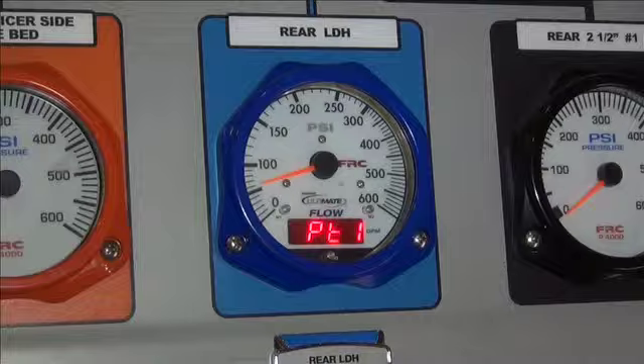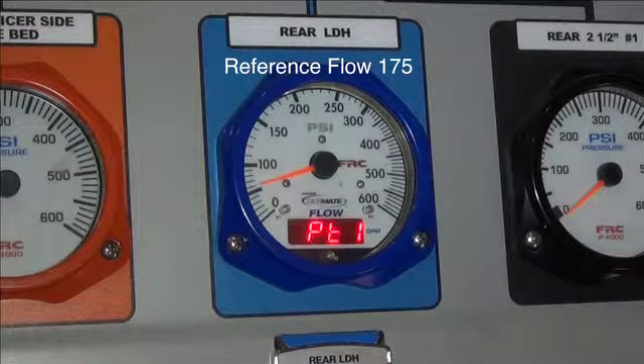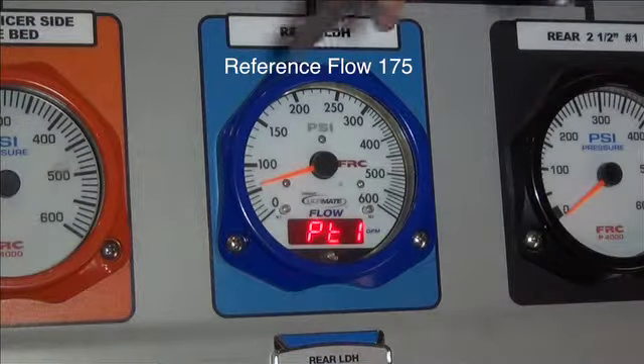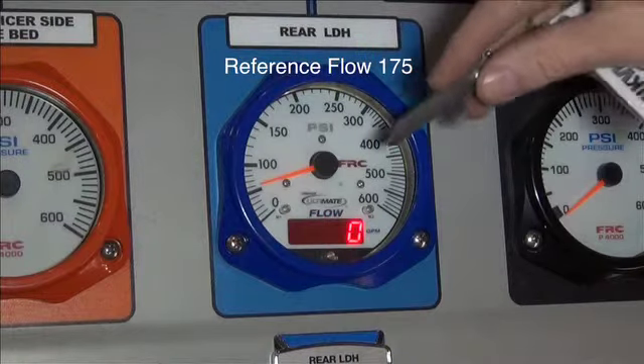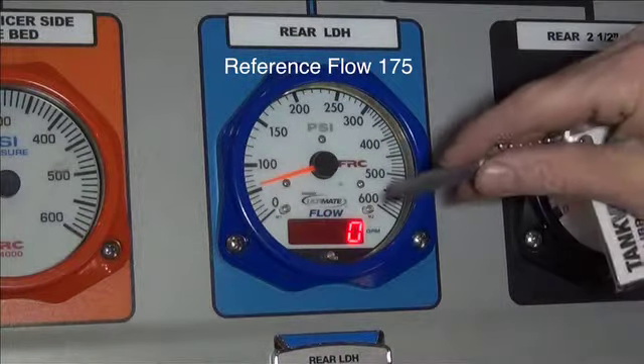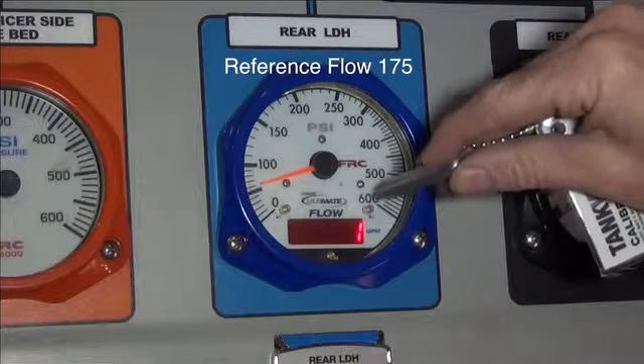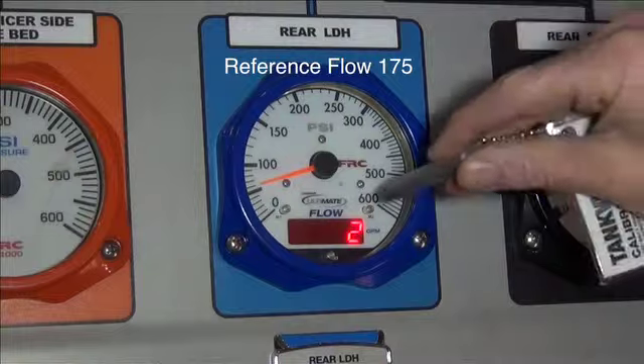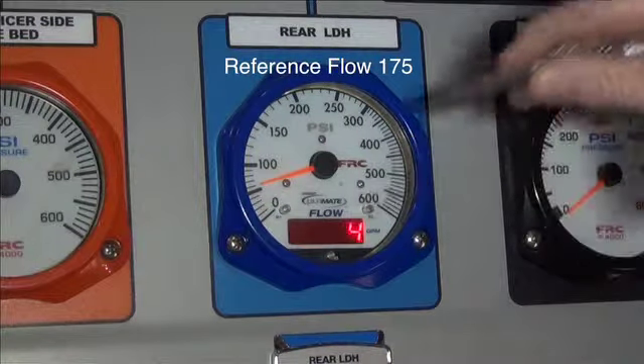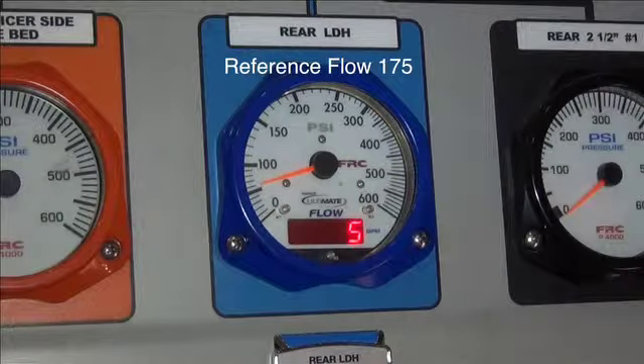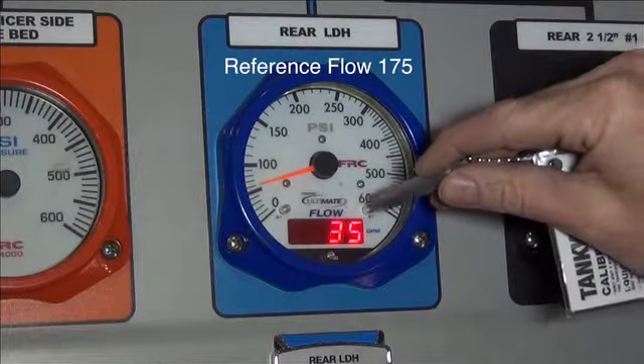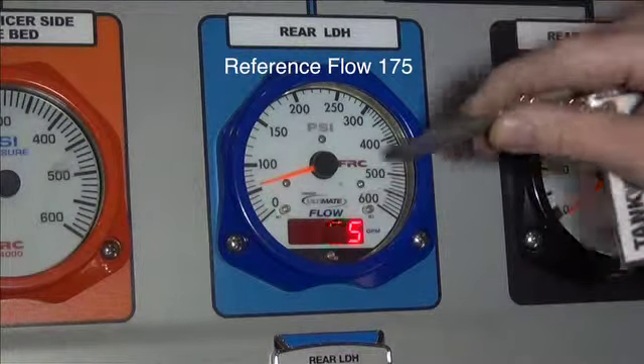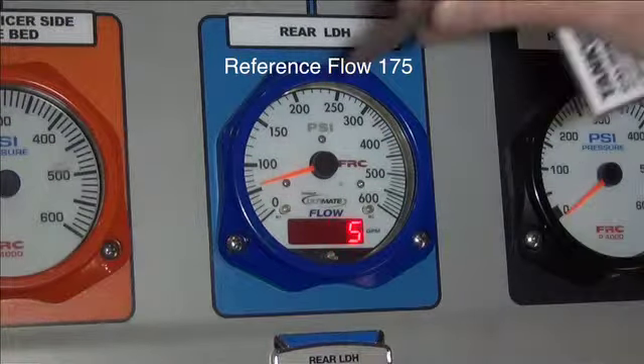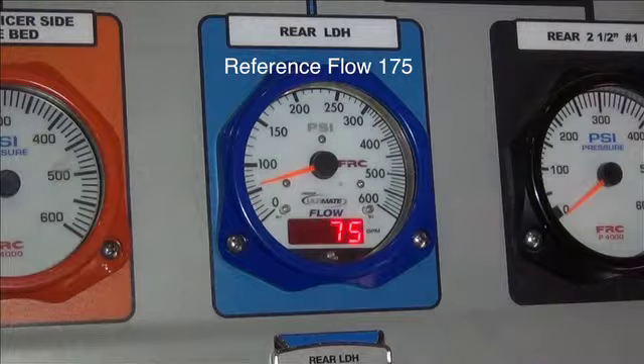Set the display to the first known water flow. In this example, the reference flow is 175. Touch the magnet to the M1 sensor to select the digit to change. Touch the M2 sensor to change that digit as needed. Touch the M1 sensor again so that the second digit is flashing, and again touch the M2 sensor as needed for the desired number. Repeat these steps until the display matches the reference flow.